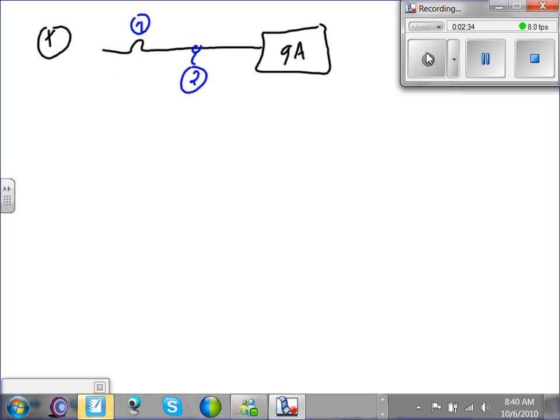It's 9 amps. My question for Spencer: just knowing it's 9 amps, does it really matter for the sizes right now if it's single phase, 3-phase, or DC? At this point, it really does not matter if it's AC or DC, for the overcurrent protection device and conductors, or 3-phase or 2 phases. So let's go ahead, and it's non-continuous.